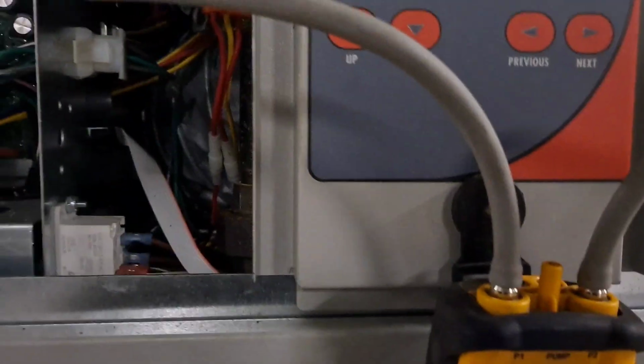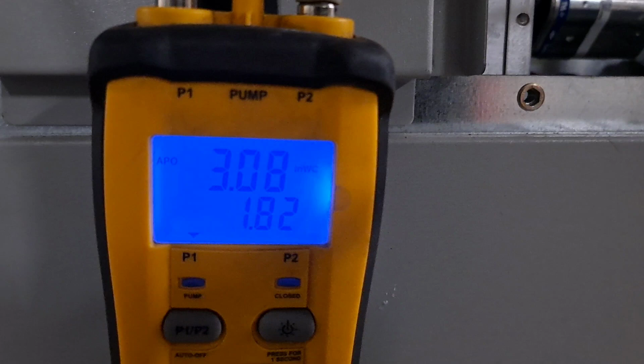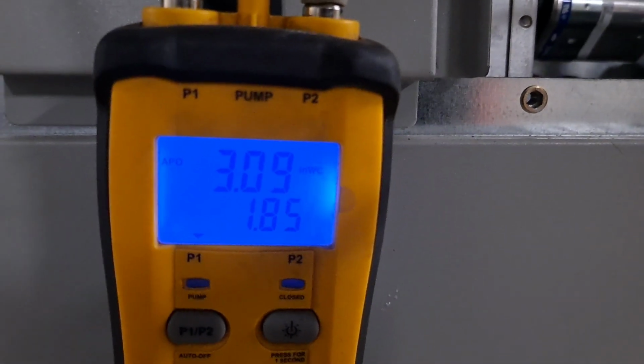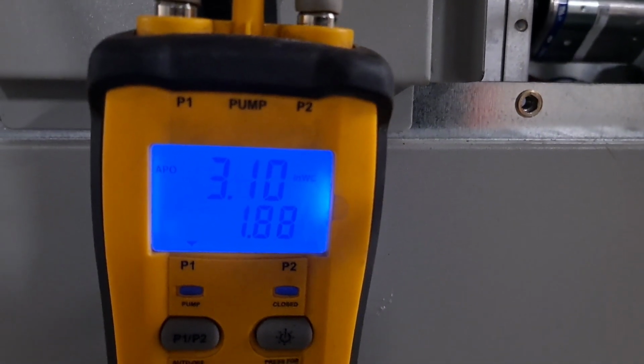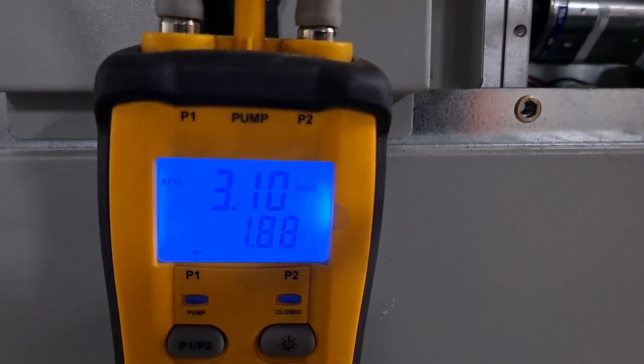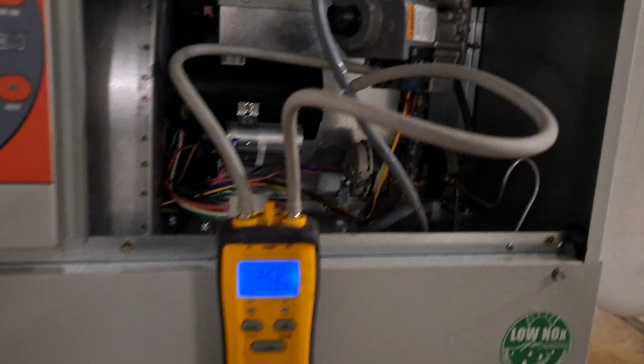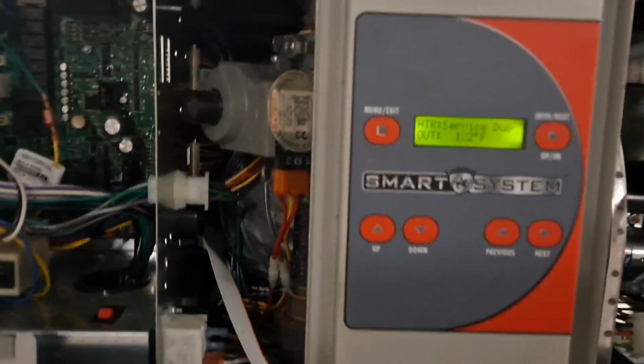And I'm at 3 inches over here on my gas valve. And my total differential, which is what the manifold pressure is, 1.8 inches, so that's pretty blasted close. Close enough that I'm not worried about it. I'm checking the second gas valve now, because there's two.